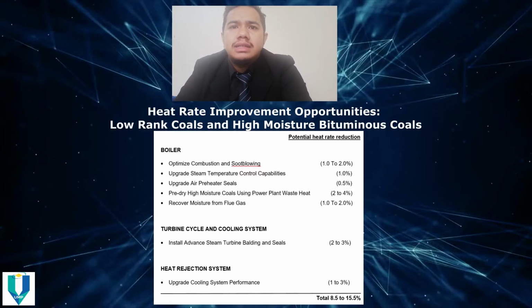Second, for the turbine cycle and cooling system, installing advanced steam turbine blading and seals takes 2 to 3%. And lastly, for the heat rejection, upgrading cooling system performance takes 1 to 3% for the potential heat rate reduction, and the total is 8.5 to 15.5% for the low rank coals and high moisture bituminous coals.